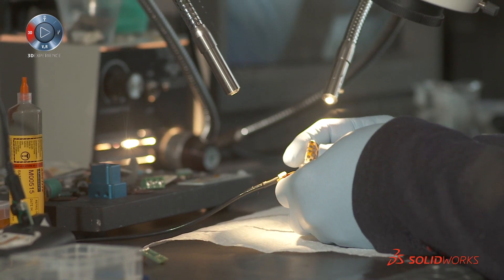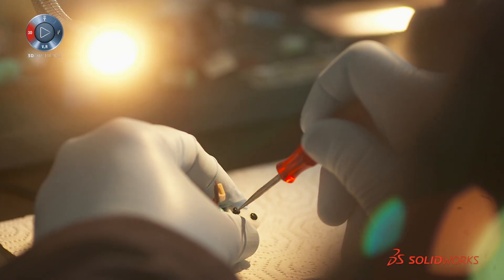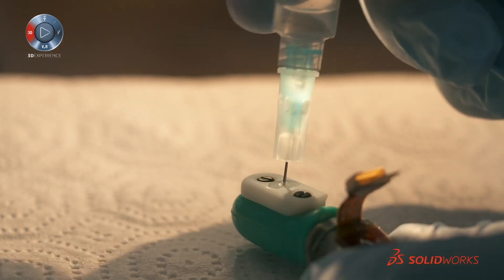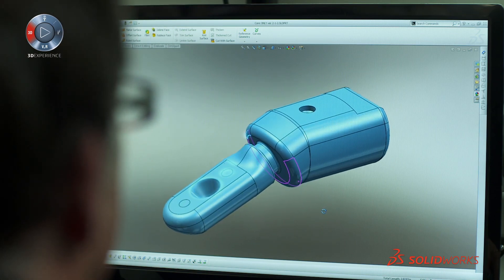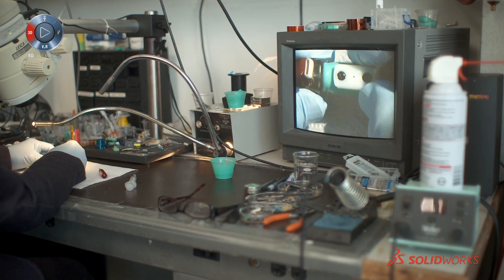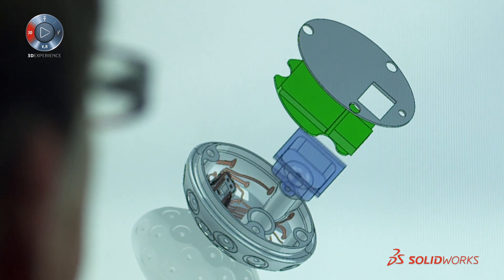At present we use a flexible circuit for our printed circuit board, which is then injected with epoxy. The electronics are buried inside the epoxy so they're not accessible, so if something goes wrong with the BioTac you don't have any way of troubleshooting it. For our next iteration of BioTac we decided we wanted something modular, so everything is independent from each other.